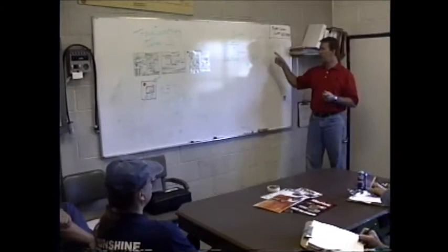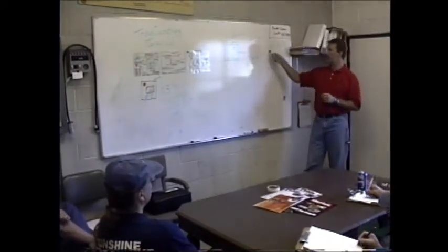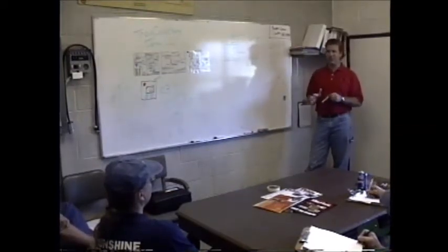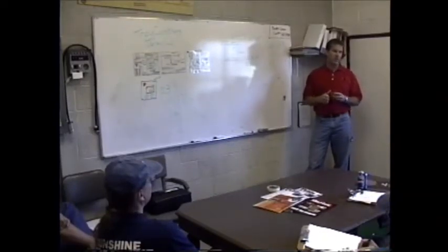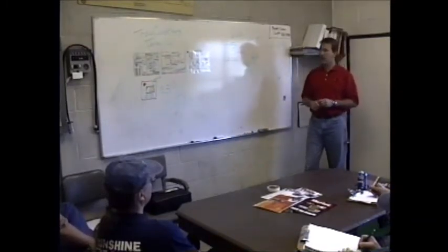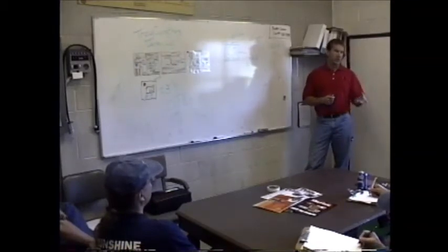Now with a 2.5 inch line, surprisingly, it's about double to a little bit more than double what you have with a 1 3/4 line. So if you can get 120 parts of stuff into a 1 3/4 line, you can get more like about 250 to 270 into a 2.5 inch line, depending upon what type of hose it is. Some of those solid rubber hoses flow different than even a double jacketed type of cotton woven hose. But the 2.5 inch lines, I really see those primarily being used to feed ground monitors or feed other vehicles or feed aerials with compressed air foam or pump into standpipes.